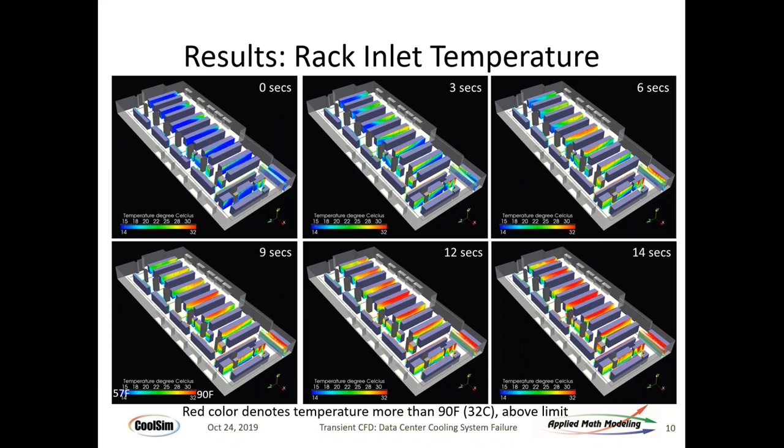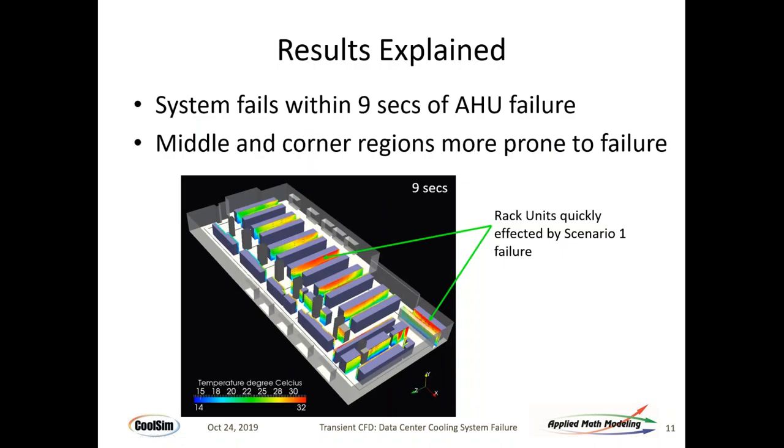Here are plots of rack inlet temperatures as a function of time. You'll notice at 14 seconds it's already hot. By the way, this is the case without containment — there are no containment systems being used here, so servers and racks have the opportunity to absorb cool air still in the room. If containment is in place, the situation gets worse because racks can't recirculate. This case isn't very interesting in the sense that you have no time — if you lose the air handlers and cooling system, it's game over in 14 seconds.